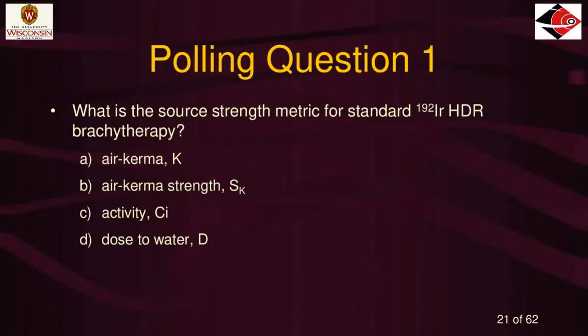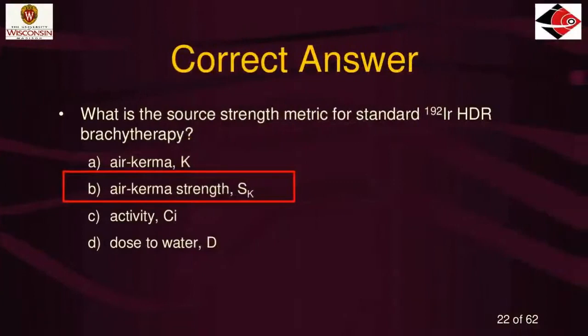Let's go ahead and review the answer. The correct answer is B, air kerma strength. Everybody's awake and paying attention — hopefully the questions get a little more challenging. The standard for an iridium source is definitely air kerma strength, measured with that seven-distance technique.